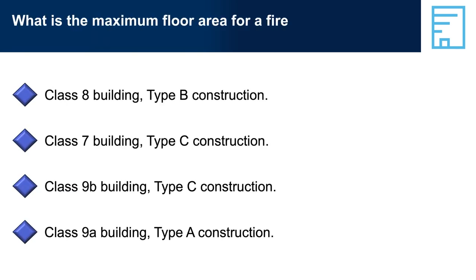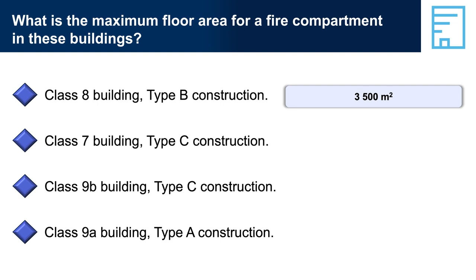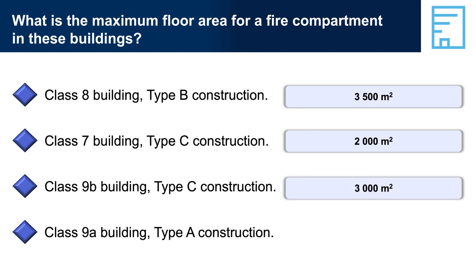What is the maximum floor area for a fire compartment in these buildings? Class 8 building, Type B construction: max floor area = 3,500 m², max volume = 21,000 m³. Class 7 building, Type C construction: max floor area = 2,000 m², max volume = 12,000 m³. Class 9B building, Type C construction: max floor area = 3,000 m², max volume = 18,000 m³. Class 9A building, Type A construction: max floor area = 5,000 m², max volume = 30,000 m³.